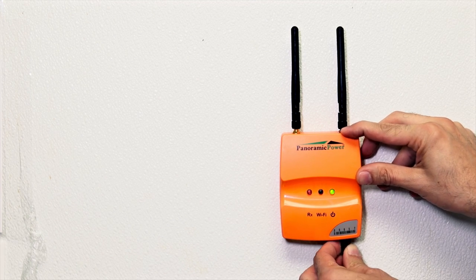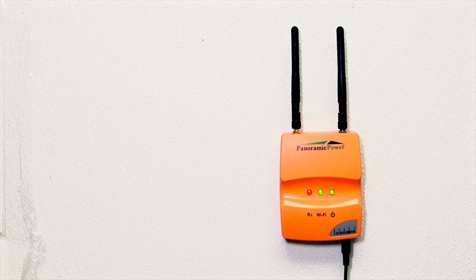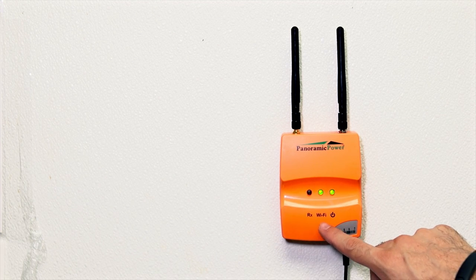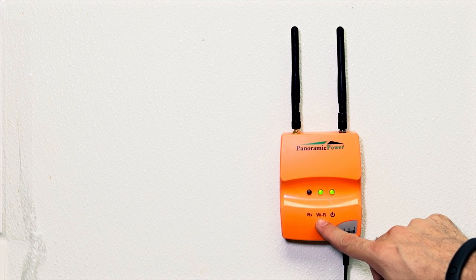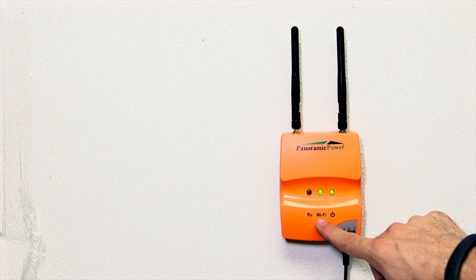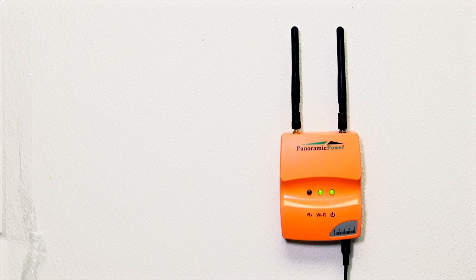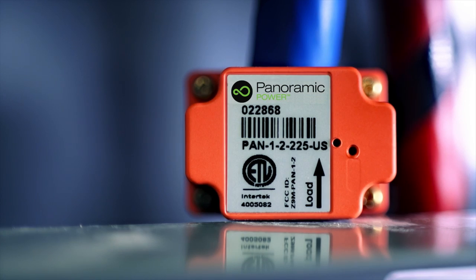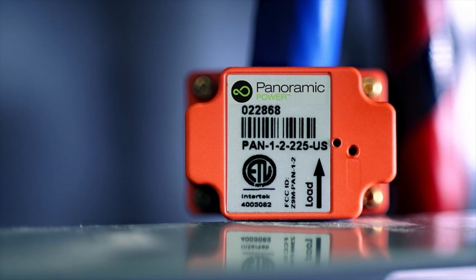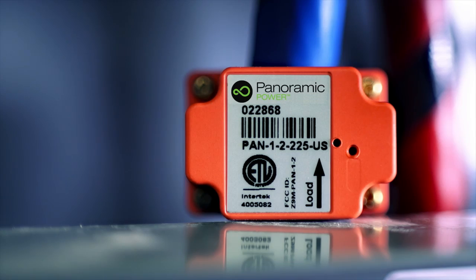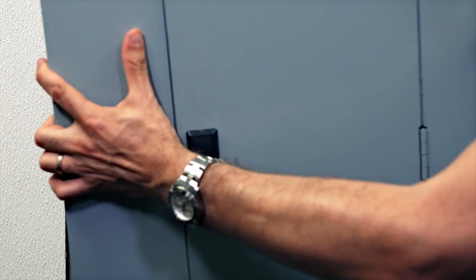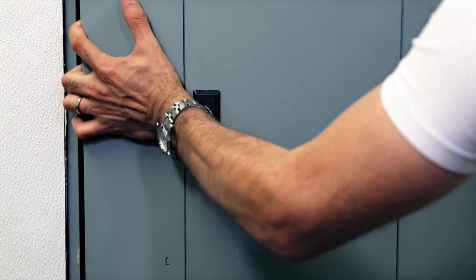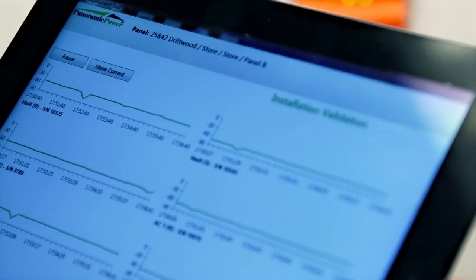The bridge communicates the energy from the sensors every 10 seconds via Ethernet, Wi-Fi, or cellular connectivity. The sensors are self-powered through magnetic fields that surround the wire, and they never require maintenance, service, or battery replacement.